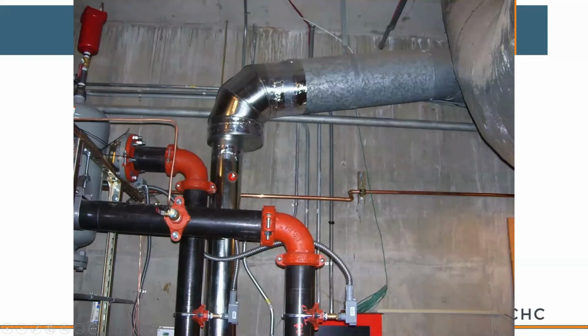Here's another example of that. They will also try to terminate here where their existing boiler was, obviously atmospheric. Here's a good example of galvanized flue. They've replaced that with a condensing boiler, more efficient, smaller vent pipe, but they're terminating it here. You can't do this. You can use this as a chase, meaning your flue gas has to carry all the way through here in the stainless vent pipe to get out of the mechanical room. But if you terminate at this spot, now we have potential to tear up this galvanized flue and do some damage. So yeah, this is another red tag issue.